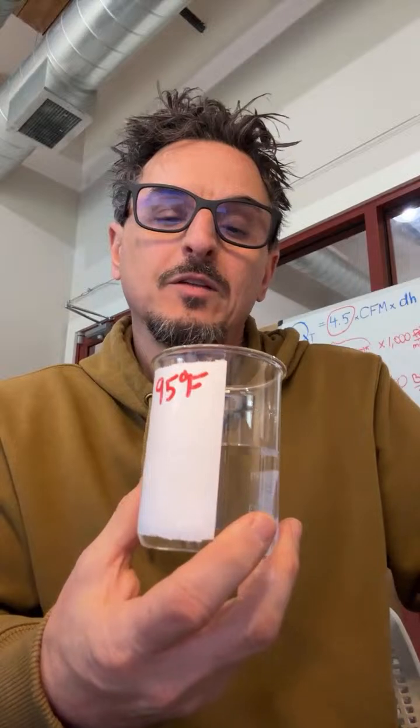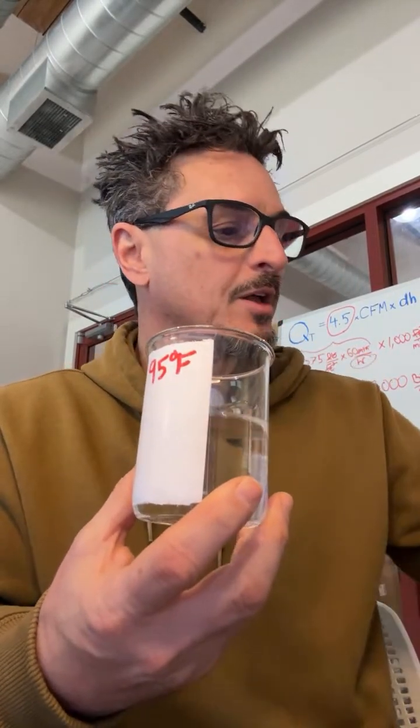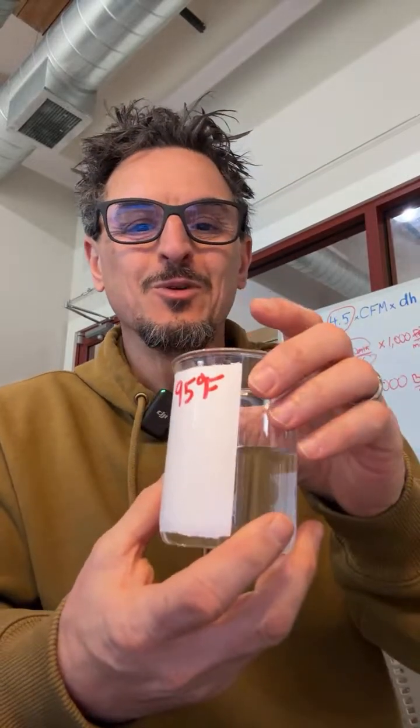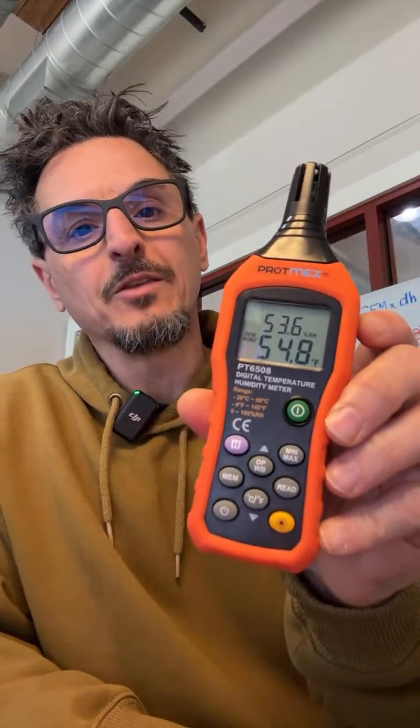But the relative humidity was not a good indicator about how much moisture is in there. So that's kind of the point here with relative humidity versus dew point. And again, the dew point is a much better indicator of the moisture in the air, okay? We could show that on the psychrometric chart, and we have a lot of longer videos on our YouTube channel that talk about relative humidity versus dew point versus humidity.